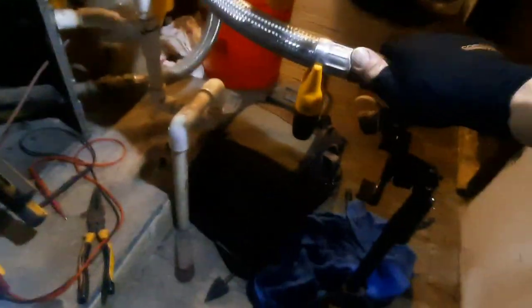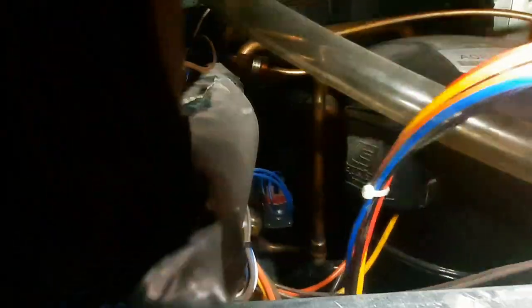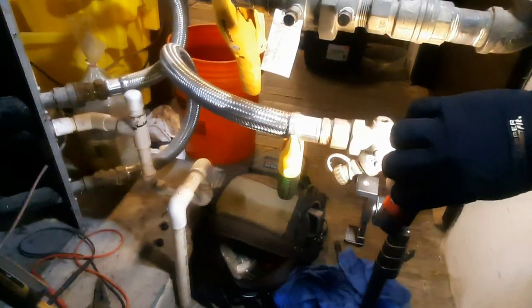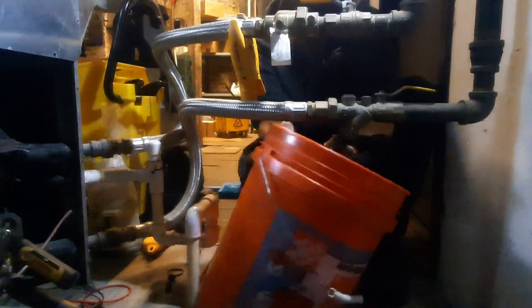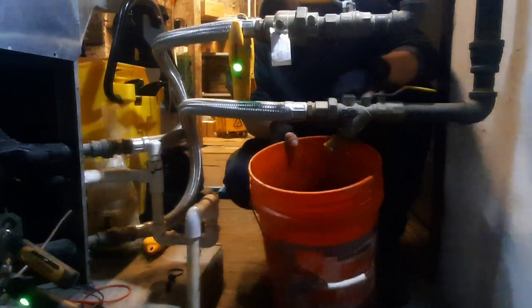I'm going to need to flush my condenser — or at this point my evaporator coil — which is that water coil. You can't even see it back in there. I don't know how you'd get to that thing, at least not on this unit. Let's flush it and see if anything comes out. We might pull the strainer. Doesn't look like I got too much out of it.